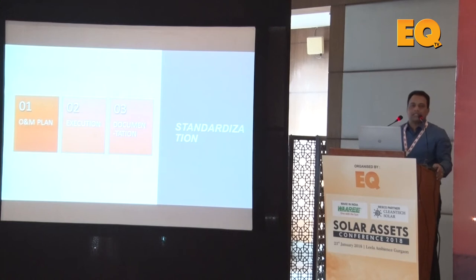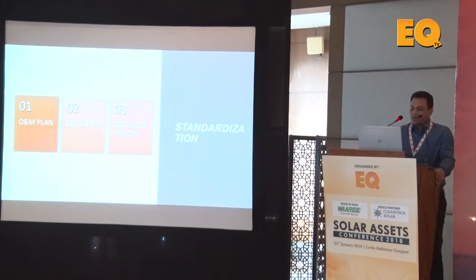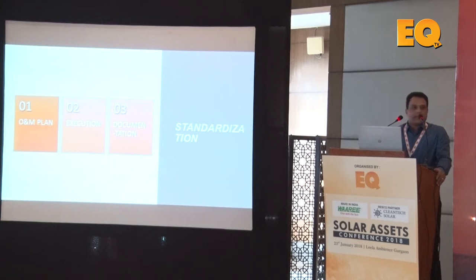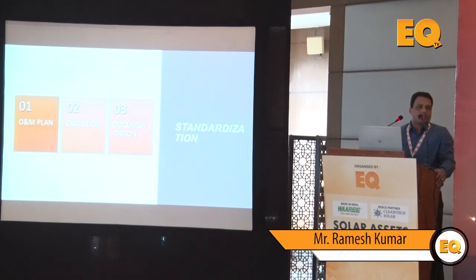The third most important thing for the rooftop sector is documentation. In my personal opinion, we in the rooftop segment are severely lacking in documentation. Proper documentation could help us save millions of rupees when talking about a 40,000 megawatt installed capacity in India. What we aim for with documentation is to isolate the site from any particular engineer — so that even someone visiting for the first time can troubleshoot problems and bring the site back into operation, by understanding the full history of any issue.